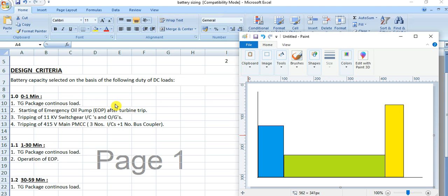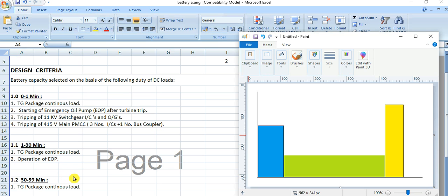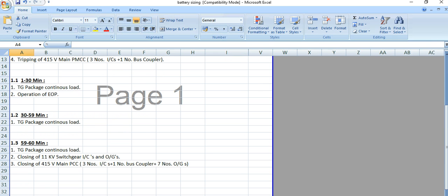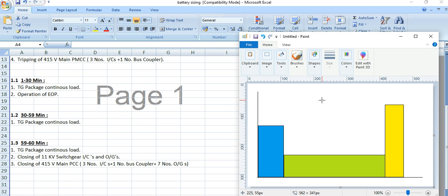For the 1 to 59 minute load, it is split into two sections. From 1 to 30 minutes: TG package continuous load plus operation of the EOP pump. From 30 to 59 minutes: only the continuous load. In most cases, this section consists of only the continuous load.